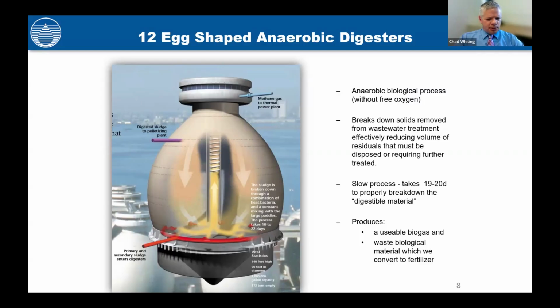And we have recirculation pumping to provide the heat for the digester as the sludge is coming out. We're reclaiming that heat through heat exchangers. And we're also attached to the primary heating loop from our thermal power plant, where we burn the digester gas. So the flow rate in the heating and mixing is between 800 and 1,000 gallons per minute to reheat that sludge and keep that digester at 98 degrees, a consistent temperature.